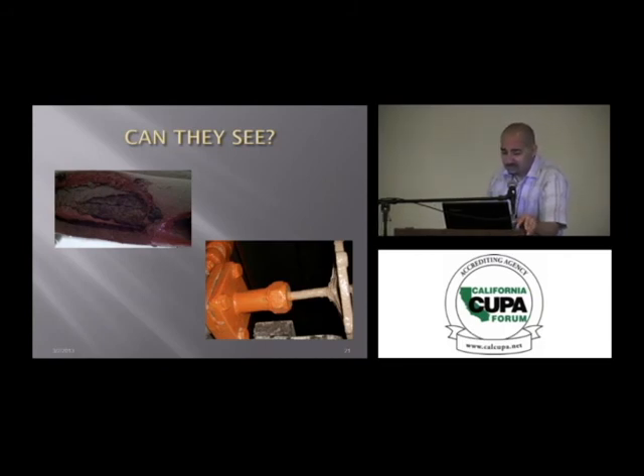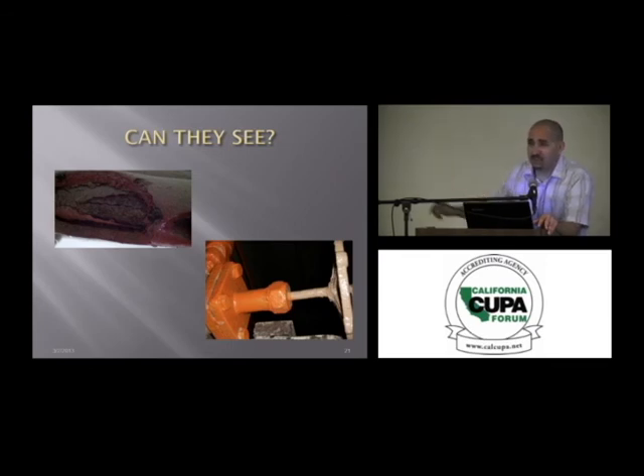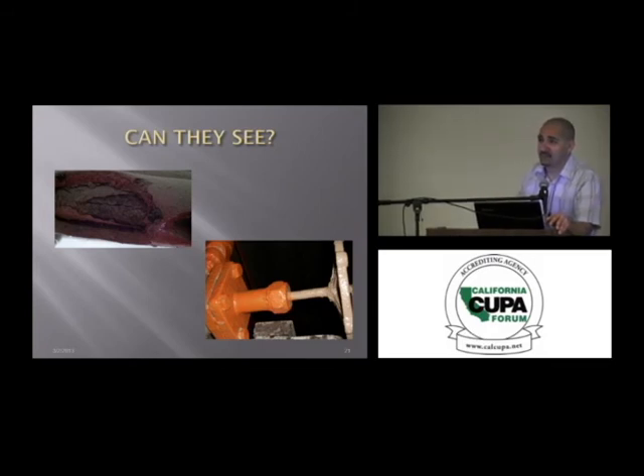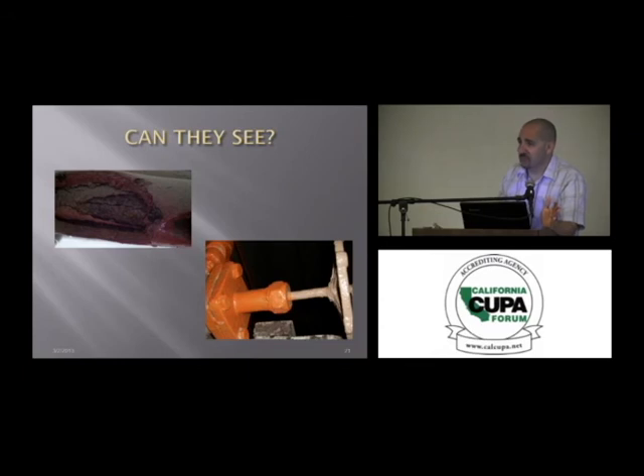High pressure liquid line, I mean, it's obvious, it's cracked. It's hard to see for you there, but there is a crack on the high pressure liquid line going through that pipe there, and that pipe has been replaced. It has been replaced. No ultrasonic thickness testing was done. I mean, you save the money, as Mike was saying. If it's feasible, don't do non-destructive testing, but just replace the pipe. Spend the money on replacing the pipe. Yeah. Make it safe. We've done hundreds and hundreds and hundreds of mechanical interior inspections, and rarely do we ever use NDT. Because almost always, 99.9% of the time, we can find the problems by looking on the outside.